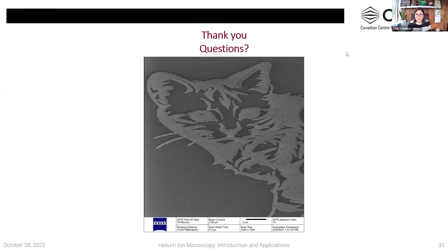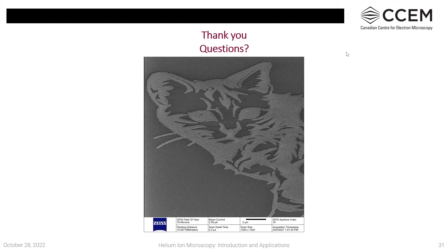Q: With the Atlas software being installed soon, could this microscope be used for FIB-SEM tomography? Answer: Yes, but it would be FIB-HIM tomography since the primary beam is helium. You can mill with the gallium beam and image with the helium beam, enabling 3D tomography.